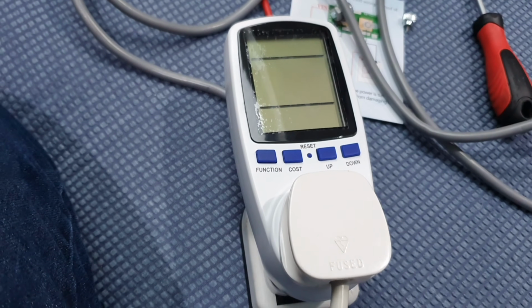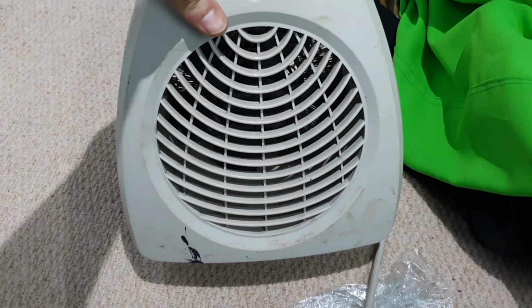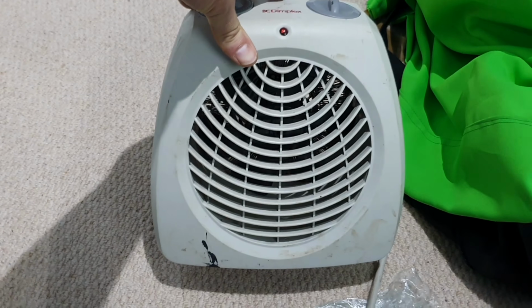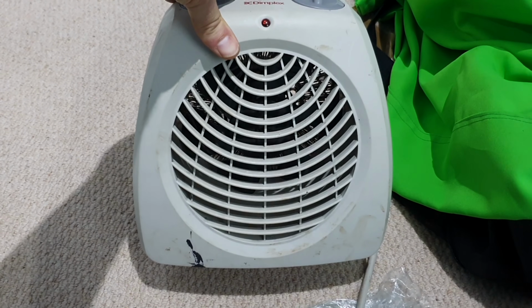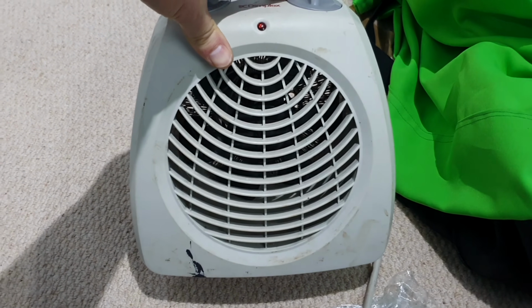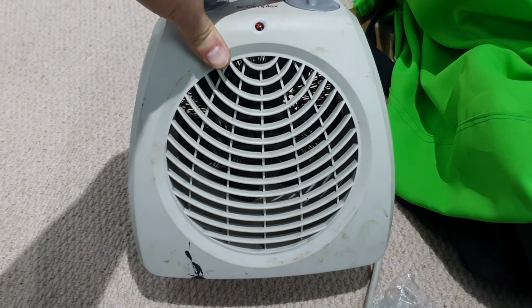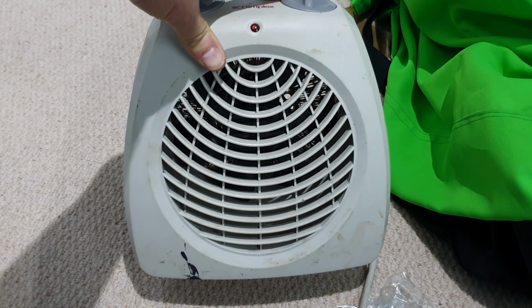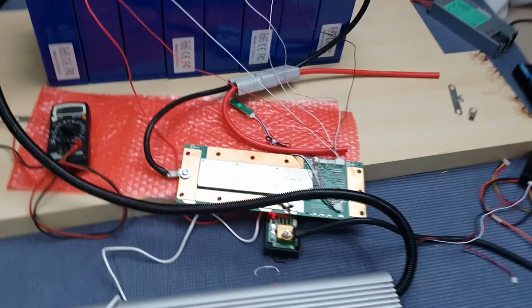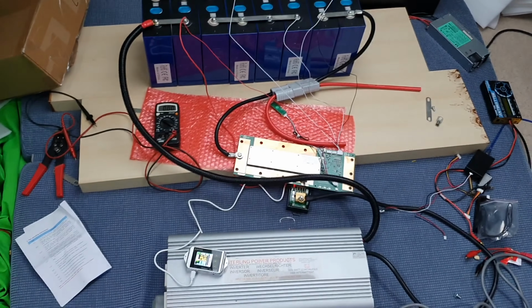I then have a 240 volt monitor connected up to the inverter, and then I've got a fan heater, which is going to be the load. This draws 1500 watts on level 2 and 3000 watts on level 3, so I'm going to use it on level 2 to draw 1500 watts. So that is the test setup. A bit dodgy here, but that's what we're going to be going with.